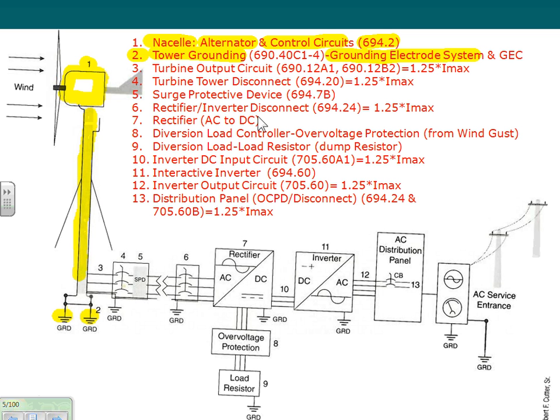But the most important thing is you have to have a ground rod, and this one is for the electrician: the grounding electrode conductor. Now we're talking technical here. Grounding electrode conductor, nothing other than a number 6 copper conductor you tie to the ground rod, typical like we do in any building. So that's the most important thing.